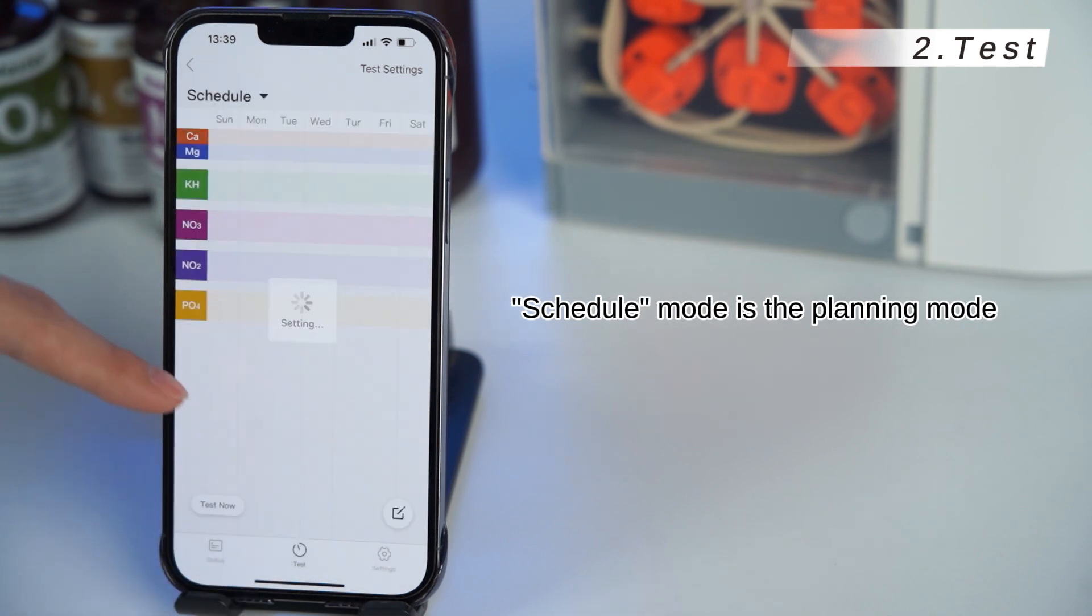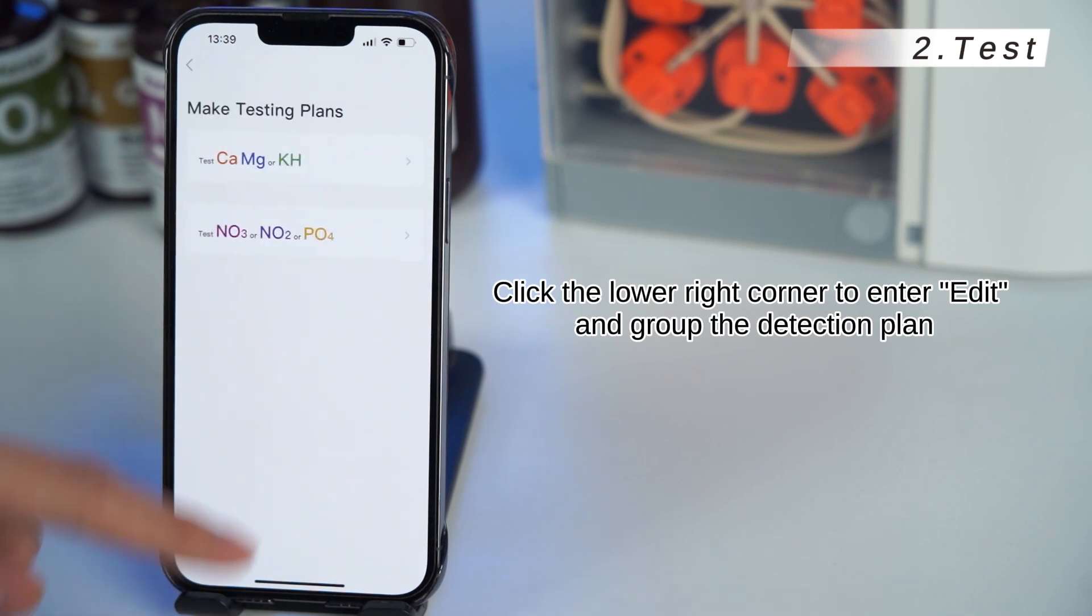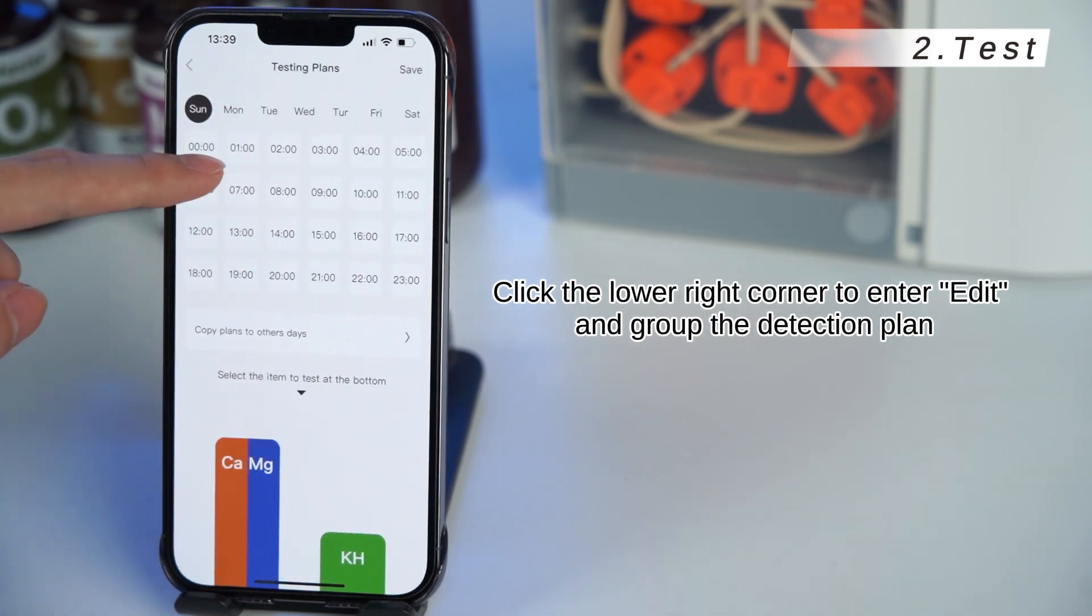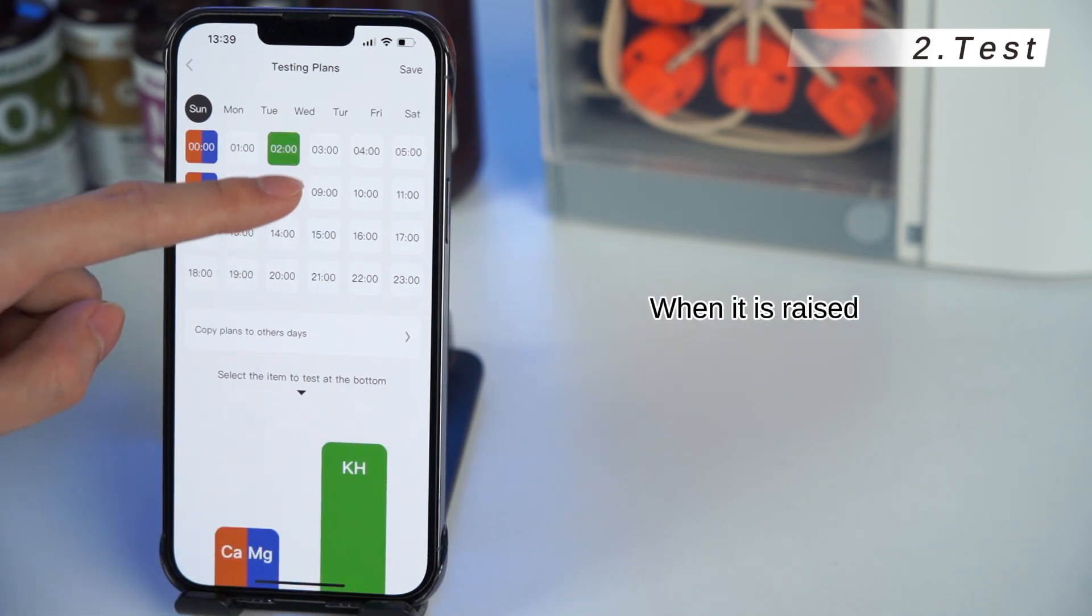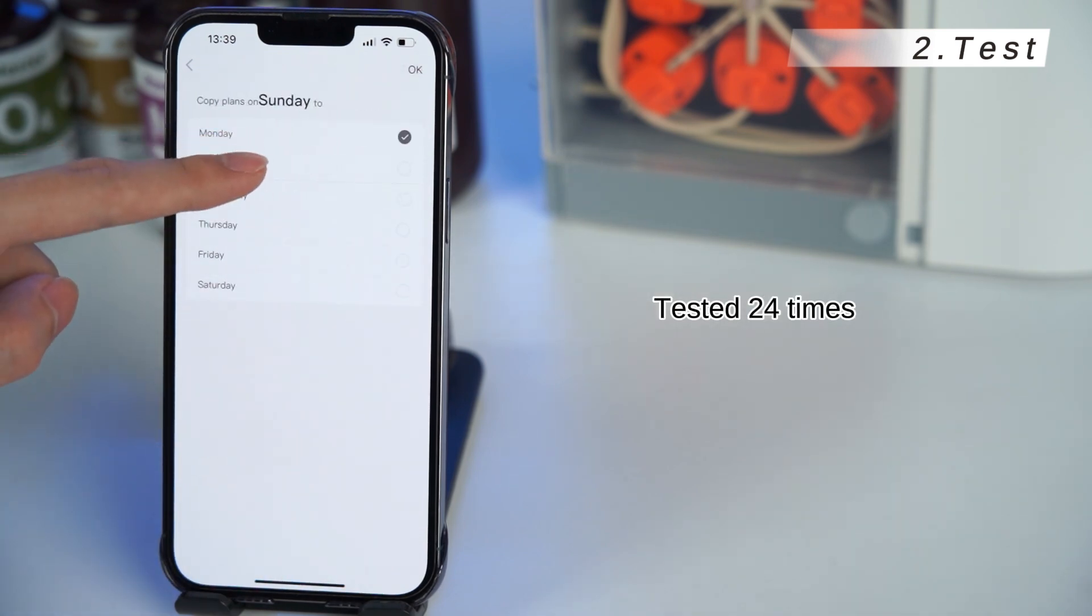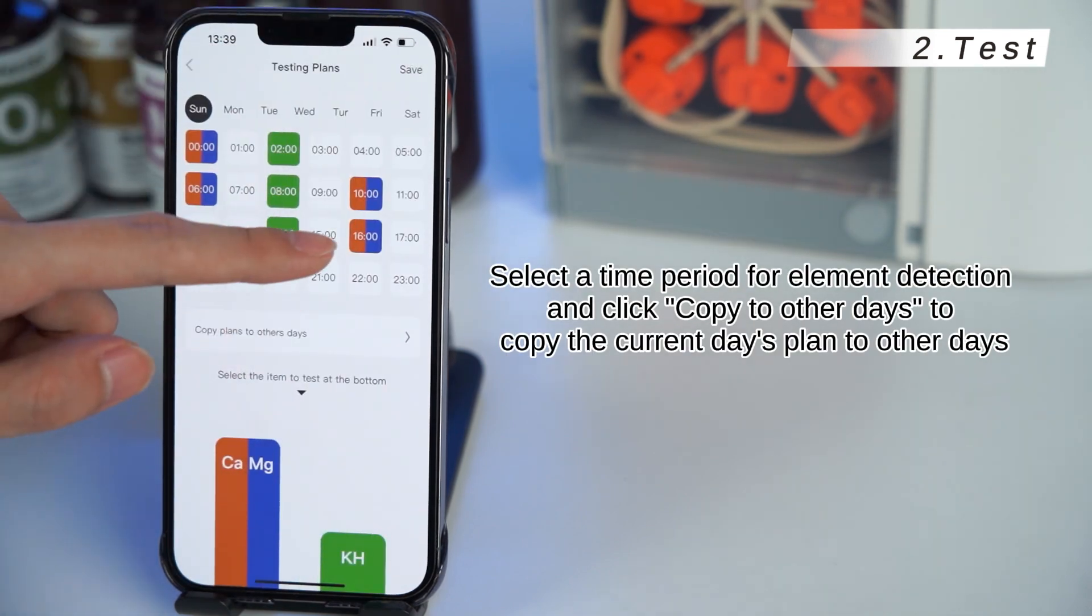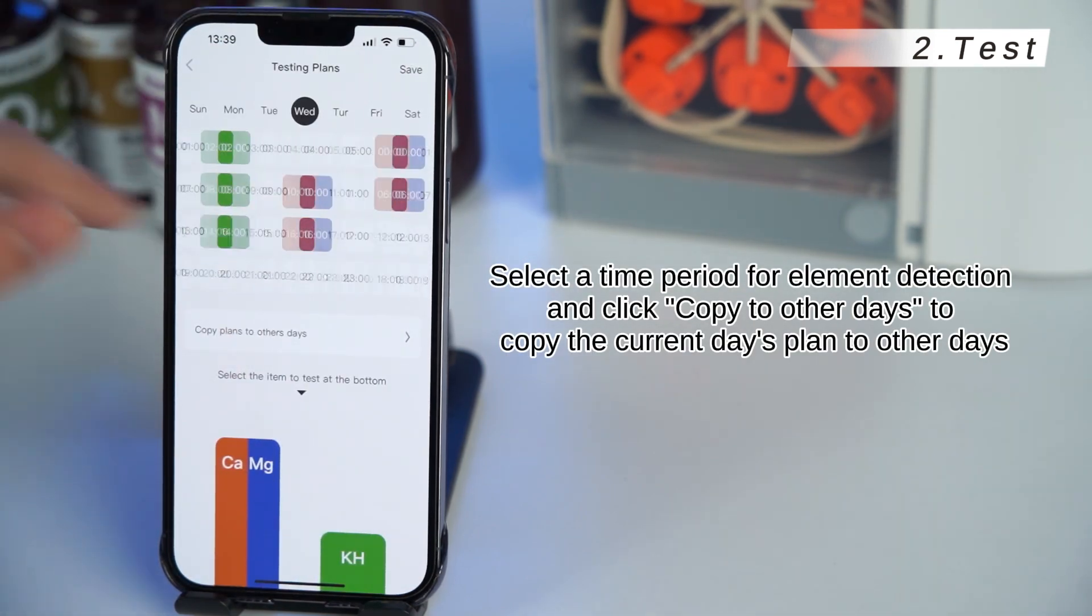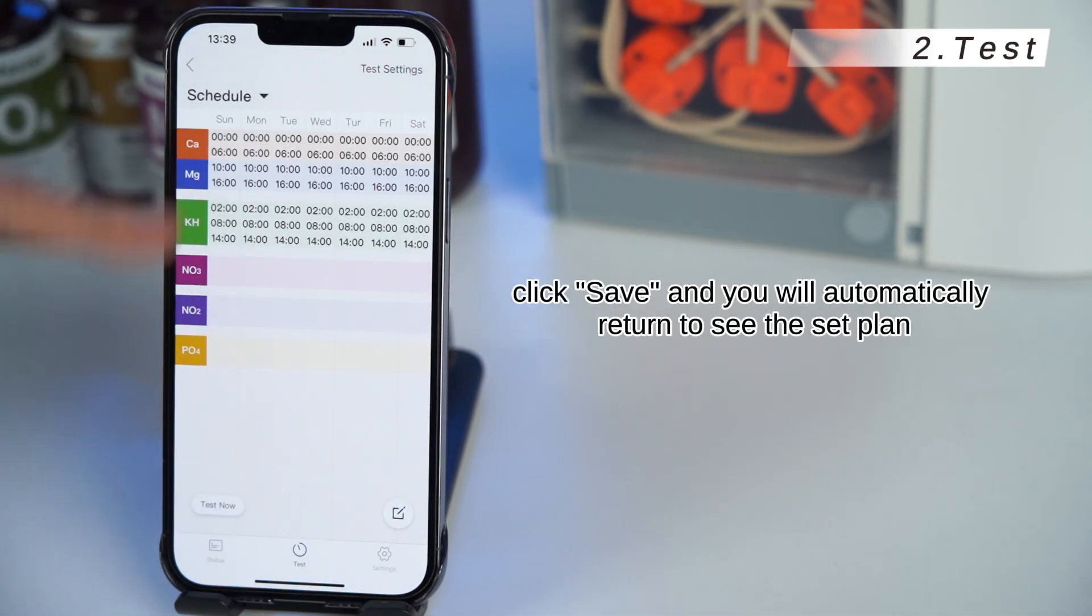Schedule mode is the planning mode, and it is also the automatic mode. Click the lower right corner to enter, edit, and group the detection plan. Click to enter the first group and select the detection element. The plan cycles on a weekly basis and can be set at most every day. Test it 24 times. Select a time period for element detection and click copy to other days to copy the current days plan to other days. After the settings are completed, click save, and you will automatically return to see the set plan.